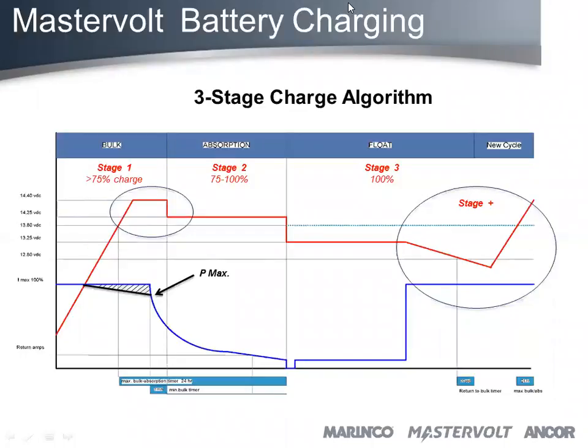Nope, it never shuts up. So you do still run the possibility that you could be gassing out the battery just a little bit? No. At 13.2, the nominal voltage of, let's say, a lead acid or an AGM battery is around 12.8, 13 volts. Yeah. So you're just above that. So there's a very minimum current flowing through that.